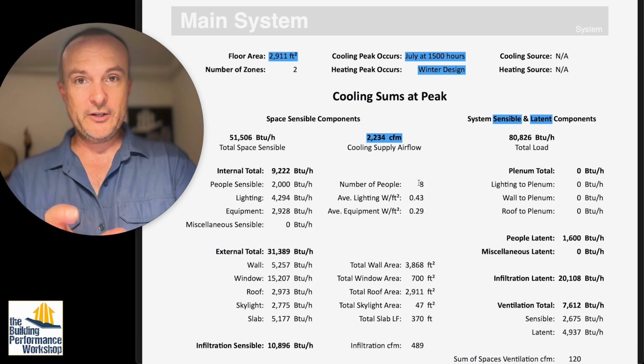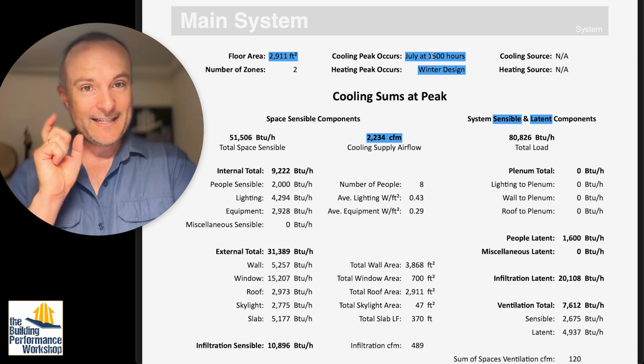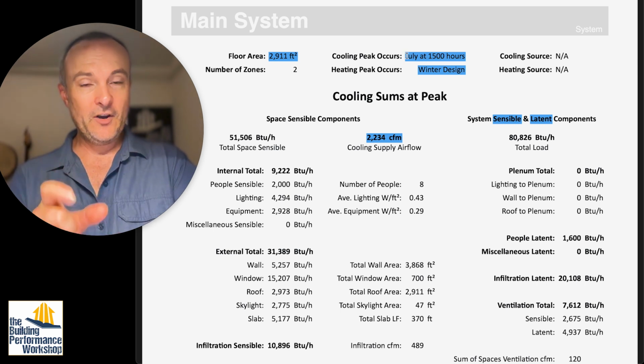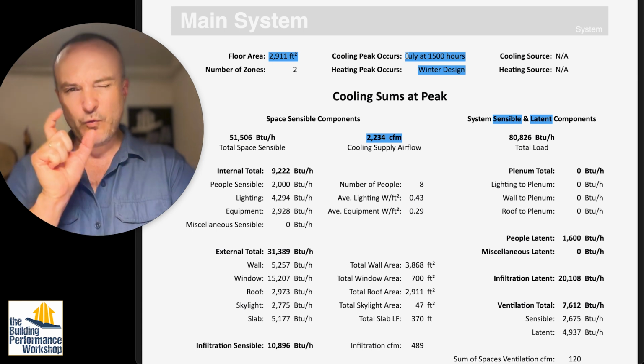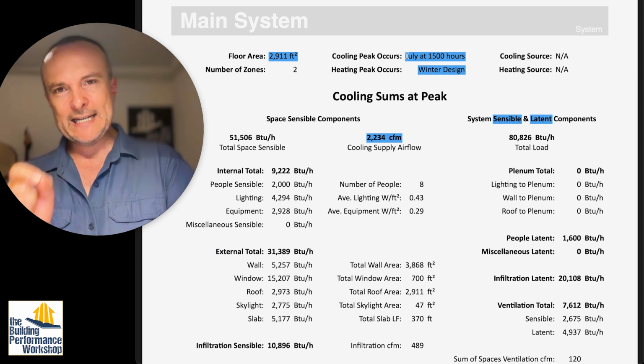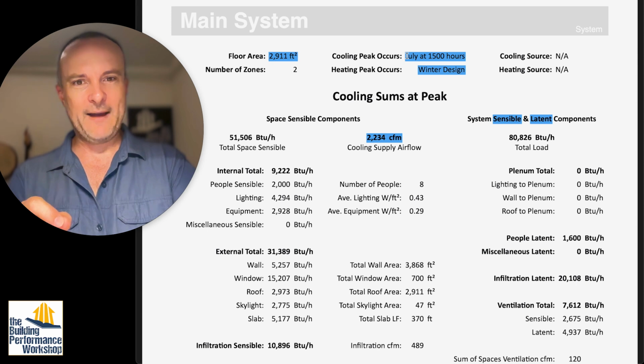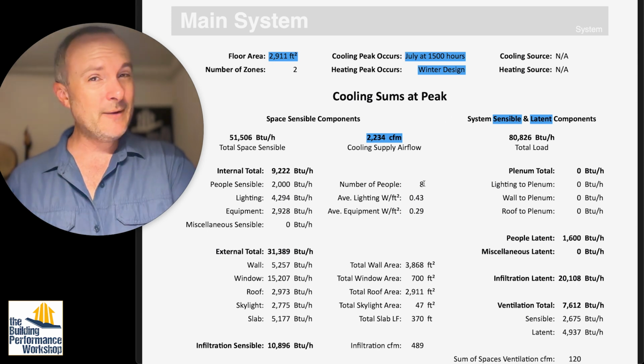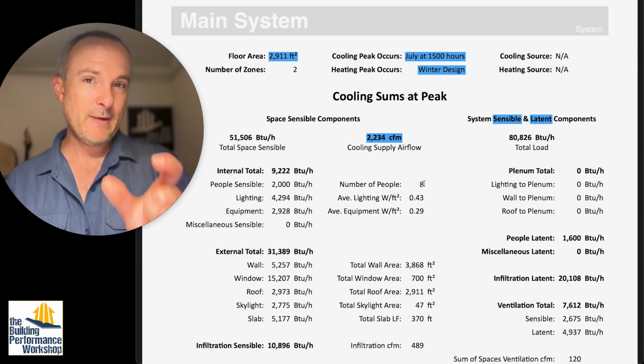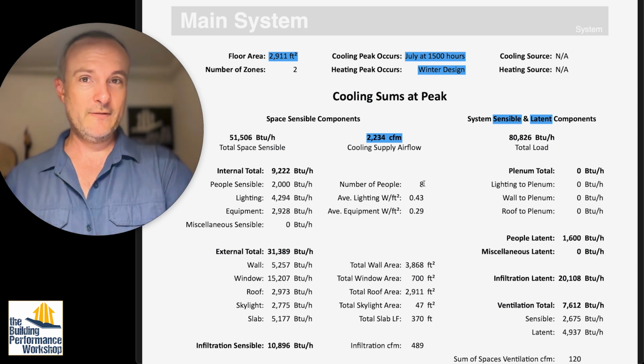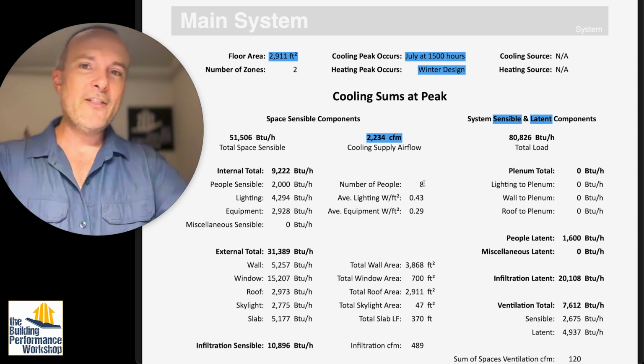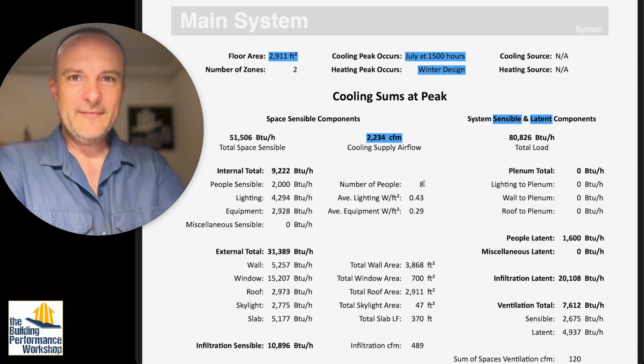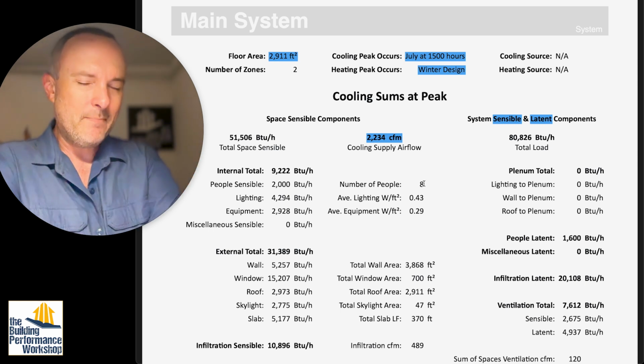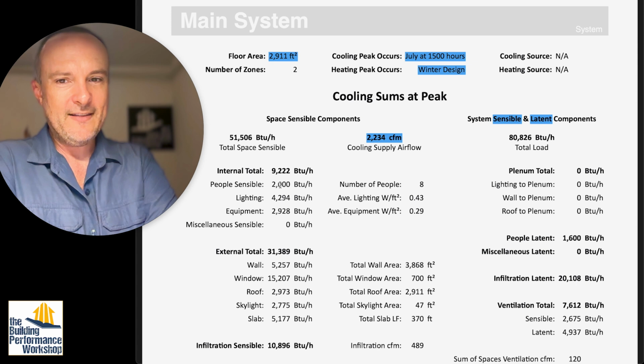Now, I will remind you that this is at 3 o'clock in the afternoon on a day in July. This is really just this one moment, the hottest day of the year at the peak temp, that we're looking at. Are there really going to be 8 people in here? That would mean that you have 7 bedrooms in this 2,900 square foot home. I doubt it. That's another clue that we're using a commercial kind of methodology when we're building this. 8 people probably don't belong in this house. So we can take this number down.